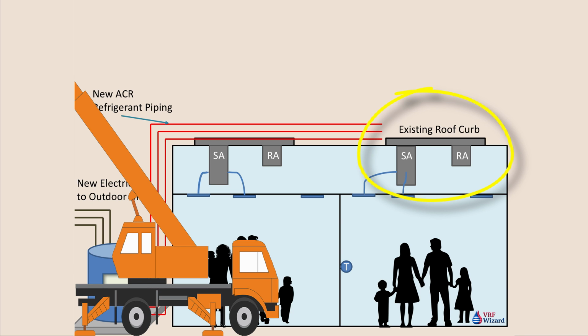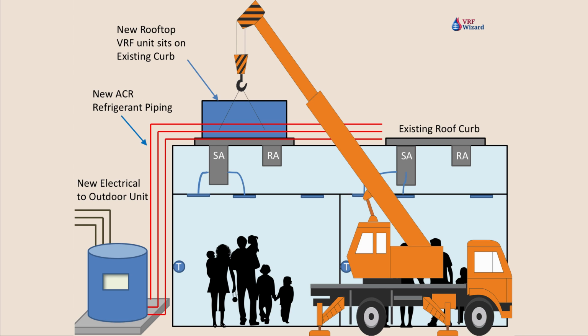the same manufacturer. If you're not using the same manufacturer as the existing units that are there, then you'll need an adapter curb, but this prevents you from having to do any work basically on the inside. And what you'll do is then drop in the new VRF package unit, which now doesn't house the compressor, condenser coil, or the condenser fan. So with a lighter unit, you get away from any structural upgrades that might be required. You're just going right back on the existing curb with a much lighter unit because the compressor isn't there, the condenser coil isn't there, and the condenser fan is not there. All that has been located in your outdoor unit.